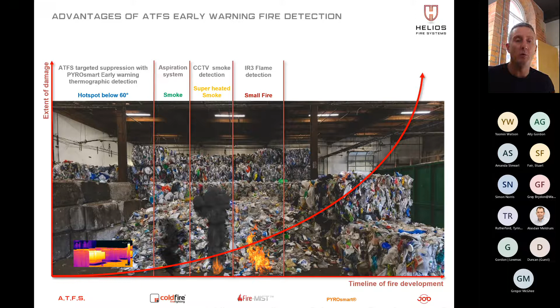Next one is IR3 flame detection. These are your standard flame detectors, your Honeywell ones or Hikvision or whatever it may be out there. Again, these systems do not work until you've got a flame. They need the algorithm or the visual image of a flame to actually see a flame there.